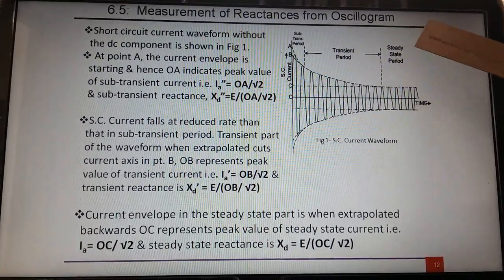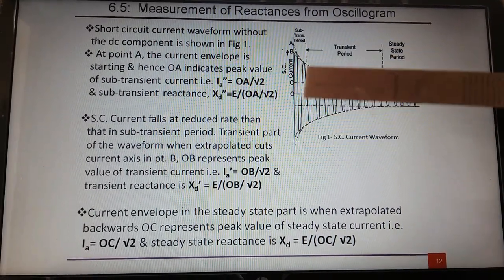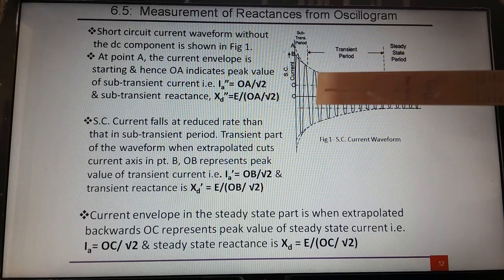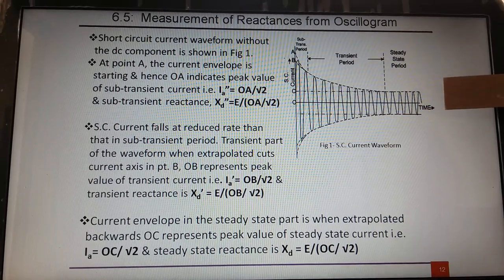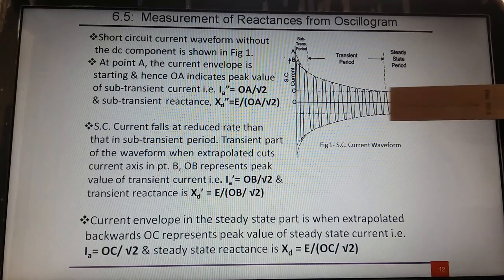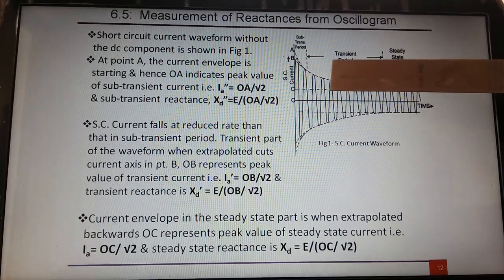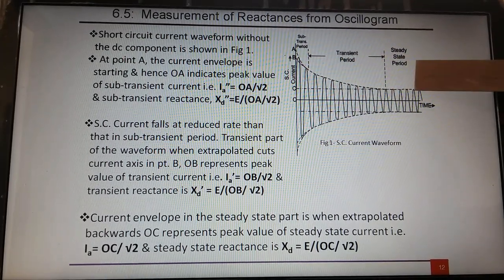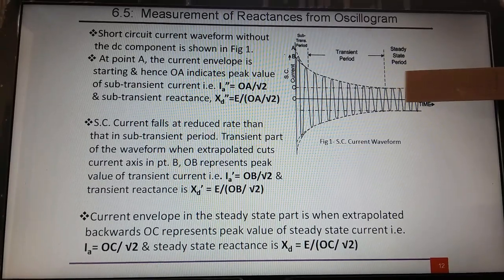This is the oscillogram of short circuit current, showing the profile of only the AC component. From this point to this point is the sub-transient period, from this point to this point is the transient period, and further it is the steady state period, where the current becomes stable and is the least. During the sub-transient period the short circuit current is largest, in the transient period it is less, and in steady state the short circuit current is least because maximum opposition is offered during the steady state period.